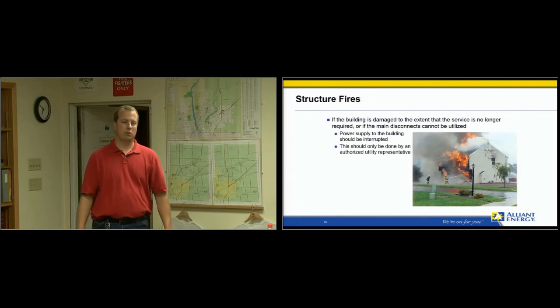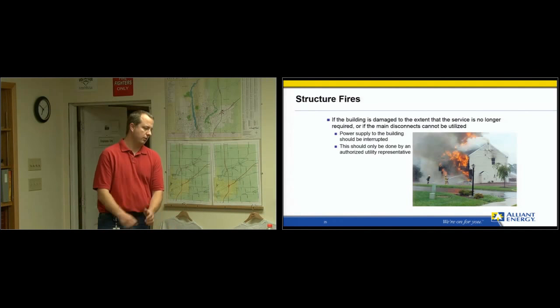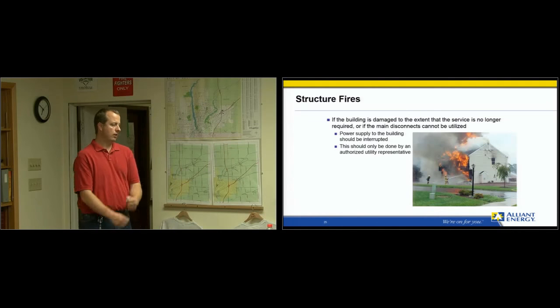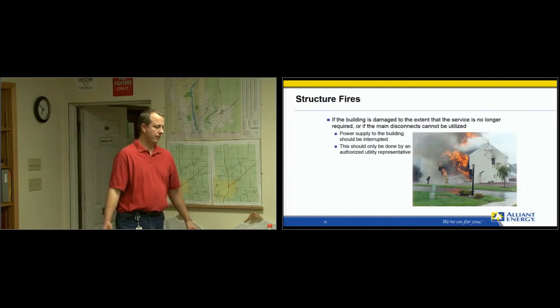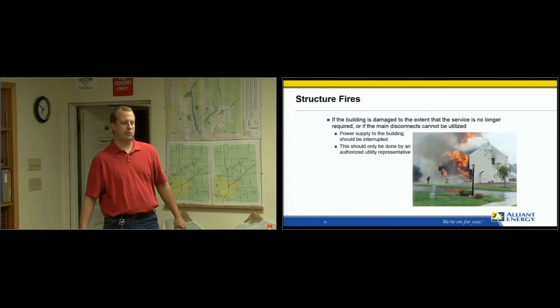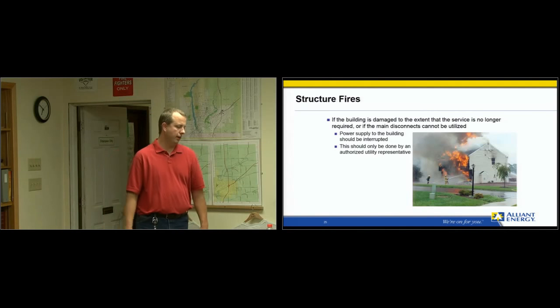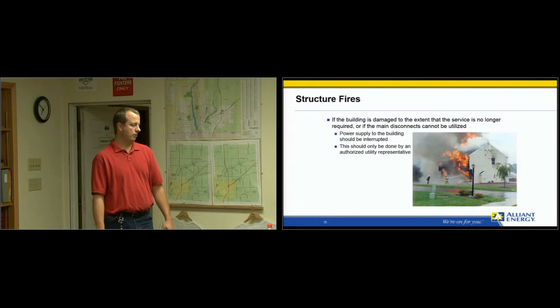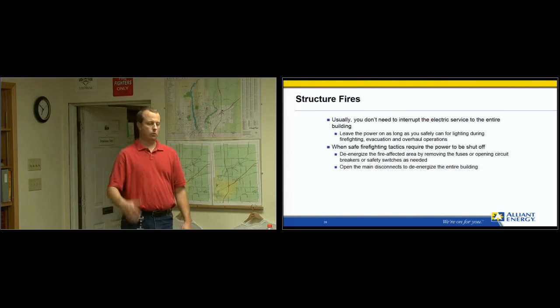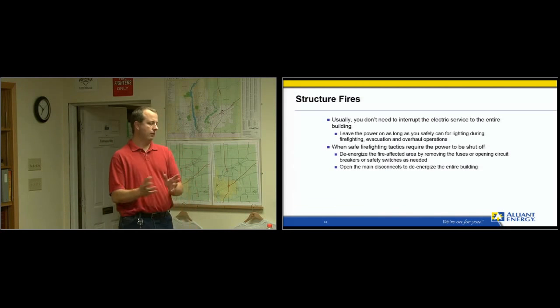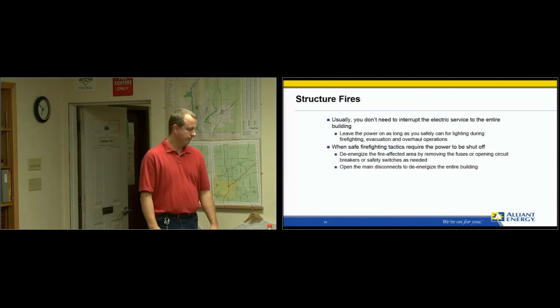So pulling that meter isn't doing us a favor—you're actually probably creating a bigger hazard. Since electricity actually flows through the meter itself, pulling it where it's not meant to be removed can create a fire or explosion hazard. Amperage and voltage will build up until it can reach ground, then it'll flash over and cause a flash.